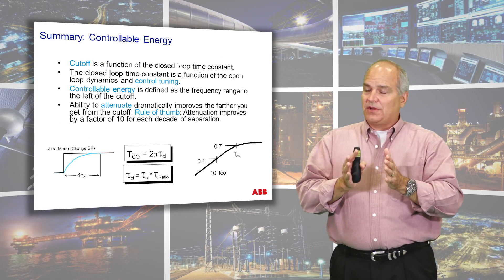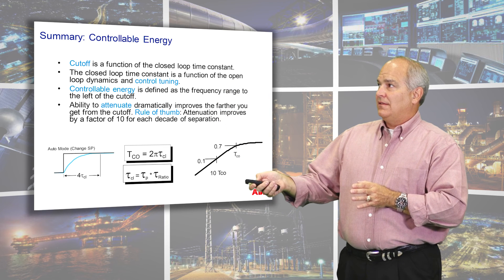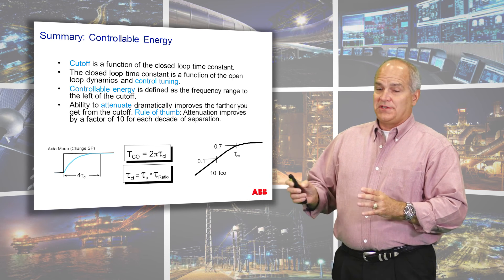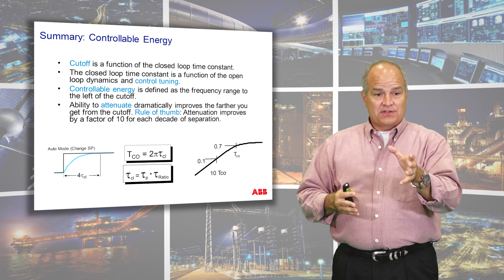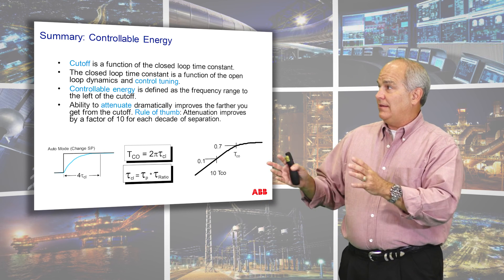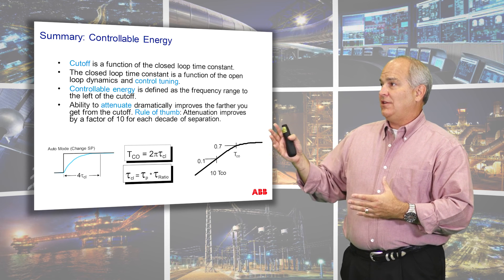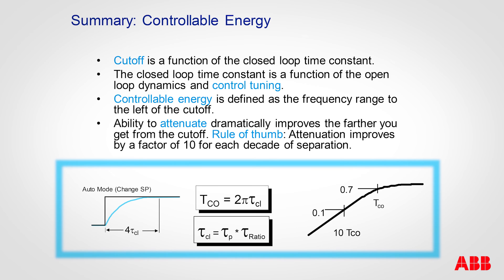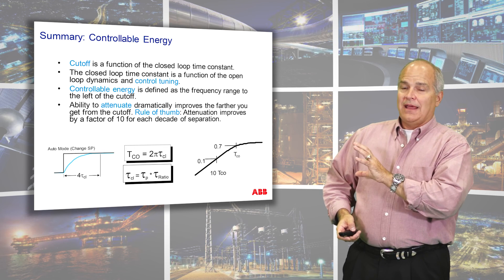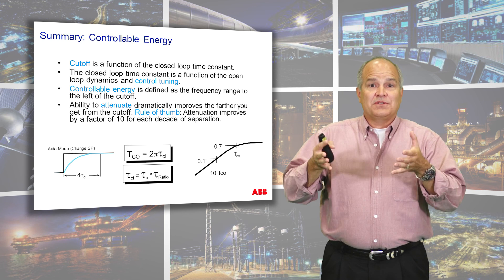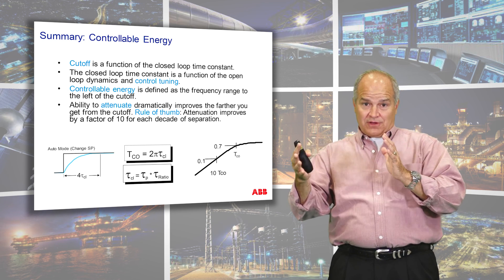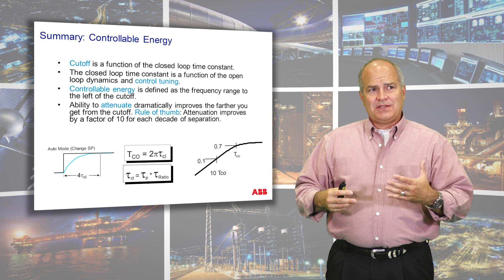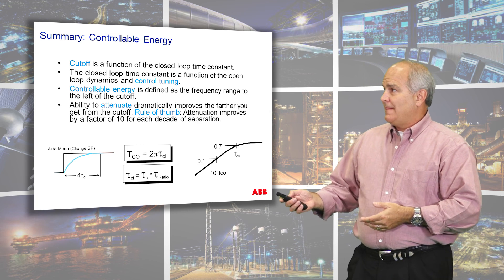The summary here: the cutoff is a function of the closed loop time constant, and the closed loop time constant is a function of the open loop dynamics. You start with a process like the tank level — how much volume do I have? Then you look at the controllable energy and where this controller is designed to operate, which is a function of your control tuning. Your ability to attenuate is dramatically improved or affected by how you tune that. Attenuation tends to improve by a factor of 10 as you move a decade away. That was a quick summary on why we're interested in frequency content: our control is designed for a frequency band. If you know how you tuned your loop, you can know how it's going to respond. But the question is, how do I know what frequencies are coming into my process? And that's what we're looking at here.